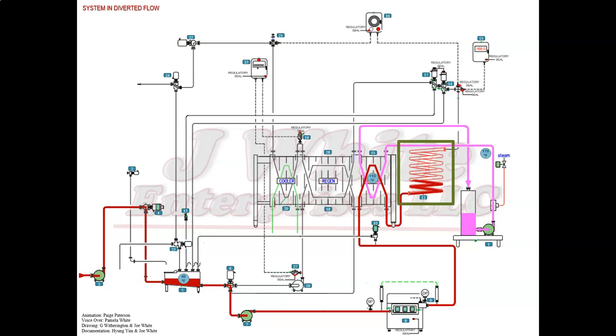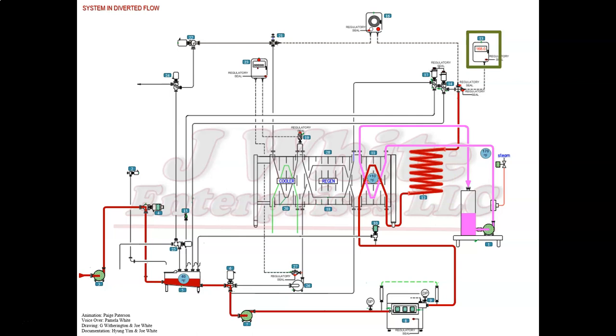The holding tube is where pasteurization occurs. This is where the product is held for the legal holding time at the legal temperature. The digital reference thermometer monitors the temperature at the end of the holding tube. It is the legal and official temperature of the product.